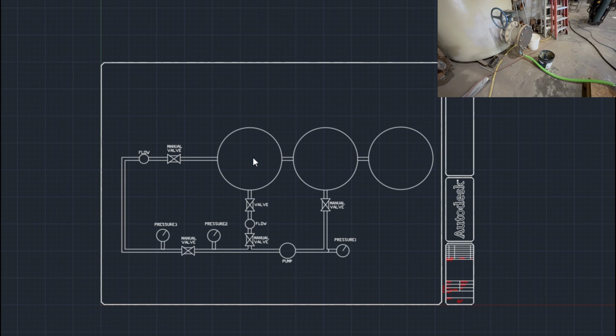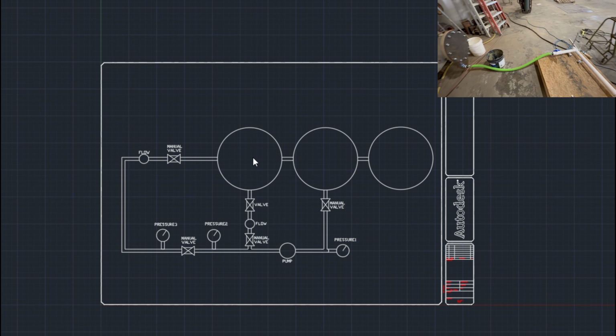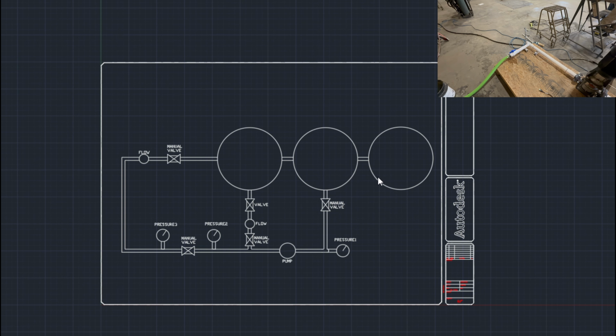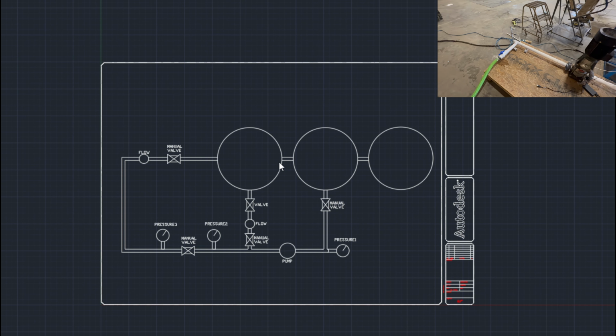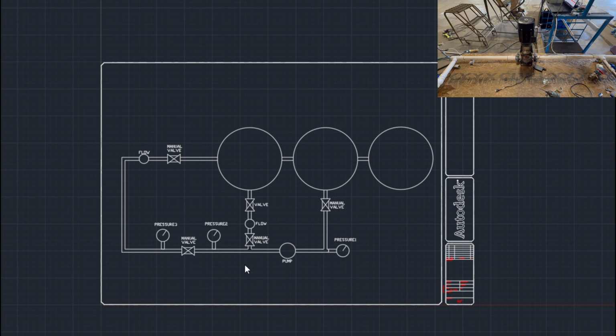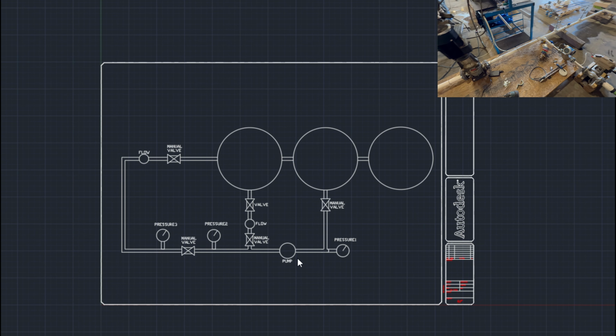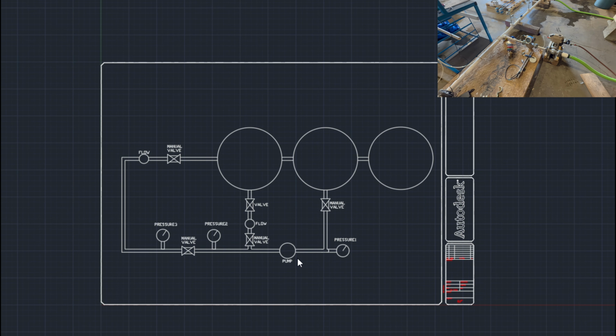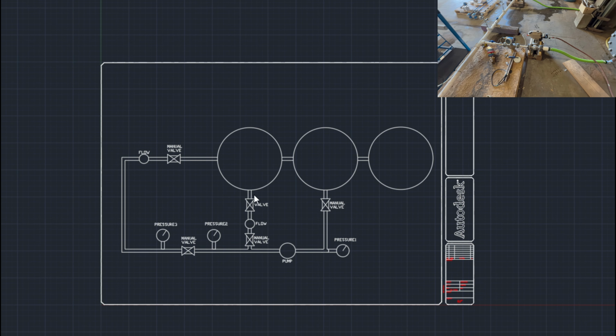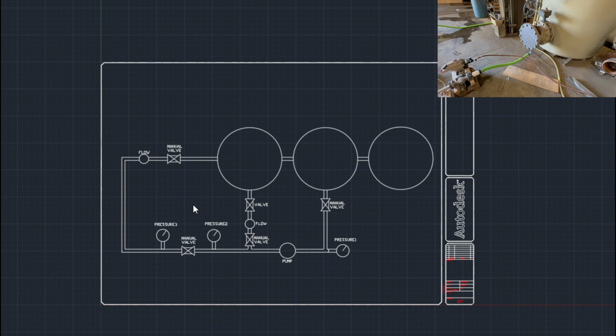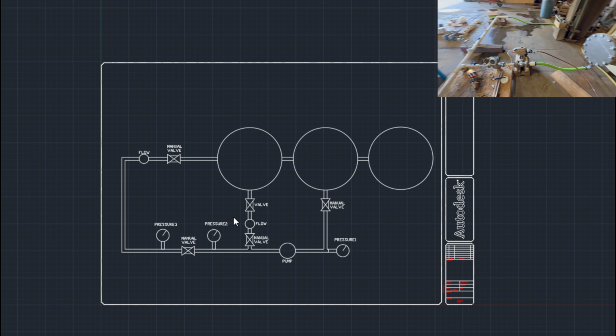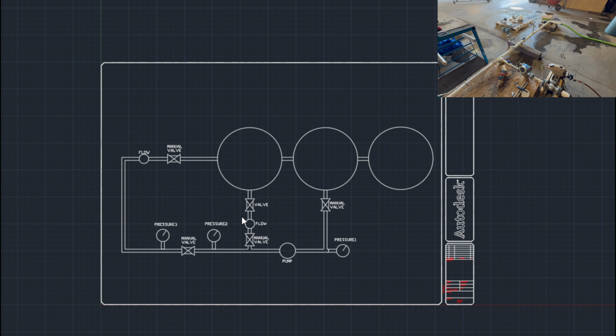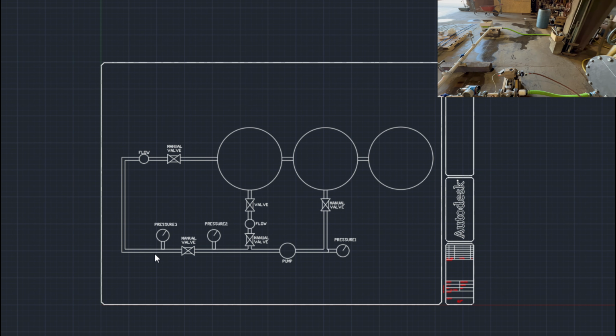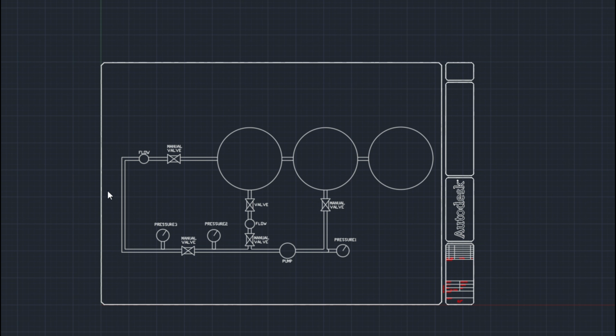To start, I'm going to show you how this system works. As you can see, we have 3 tanks here, but we're only using 2 of them. What we're trying to do here is simulate a 1-pump booster station that keeps a constant pressure, but also a constant flow. We're treating this area here as if it were a town or house that is using water, and we have it set up to keep a constant loop so we don't have to worry about low levels or anything like that.